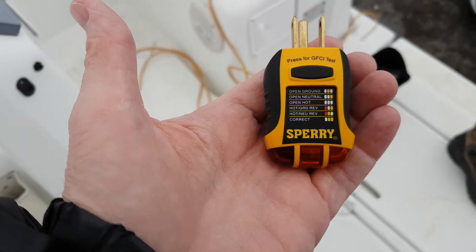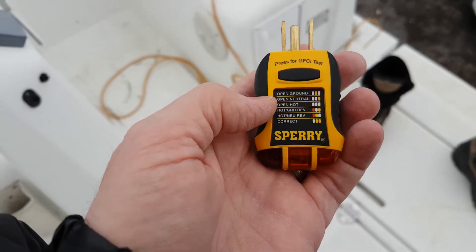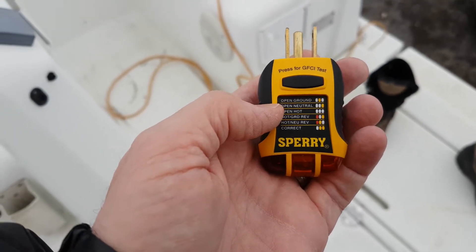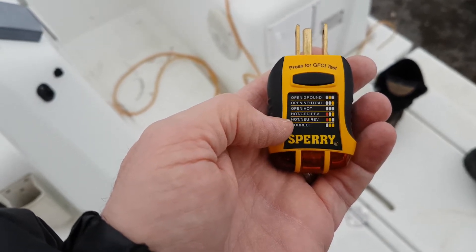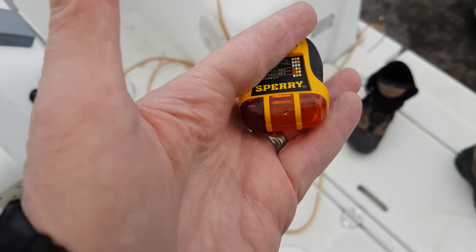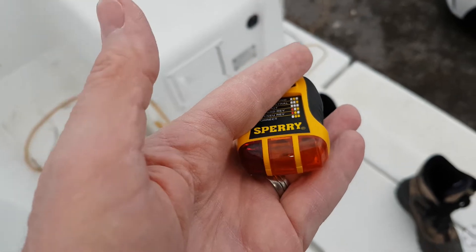Good morning, today I'm going to be working on my electrical system and I wanted to show you one of these neat tools I picked up on Amazon. I got a Sperry GFCI tester that also tests a bunch of different faults in your wiring: open ground, open neutral, open hot, hot-ground reverse, hot-neutral reverse. If everything is correct, these two lights here will be lit in orange.